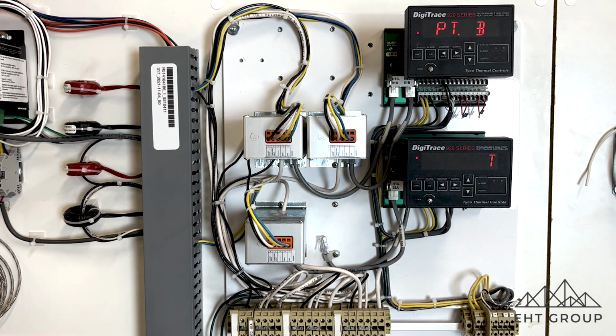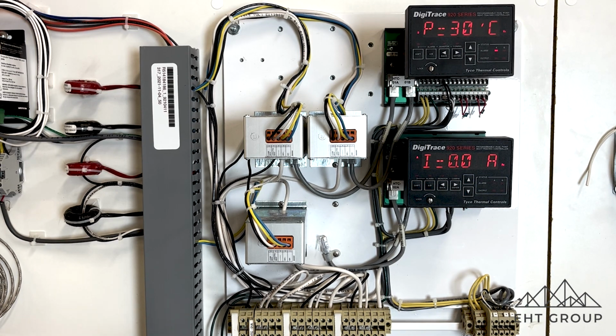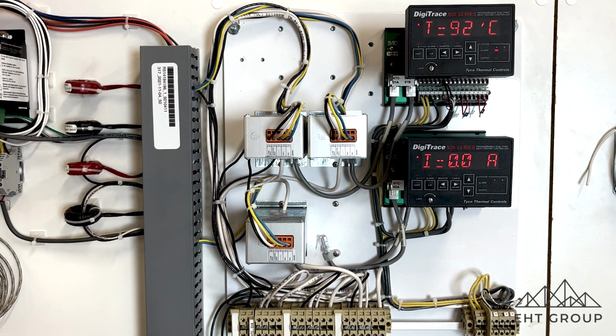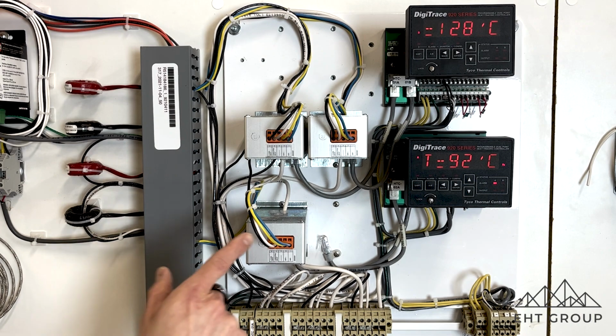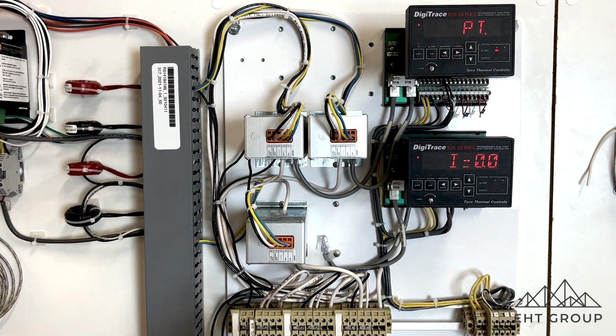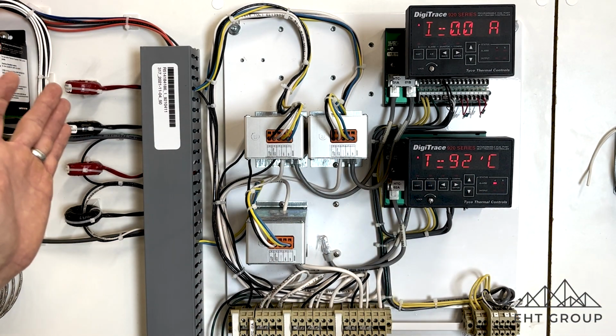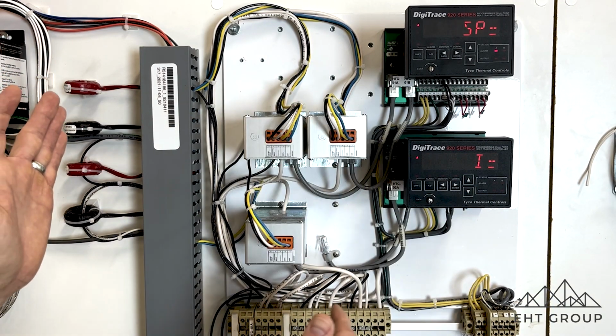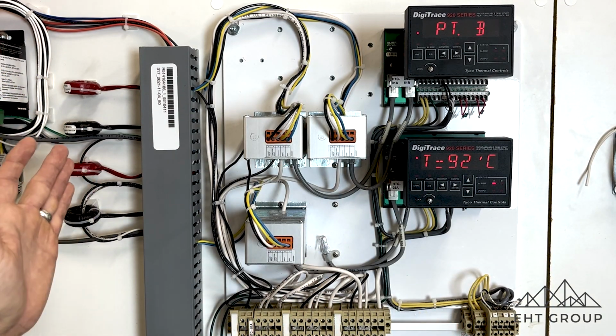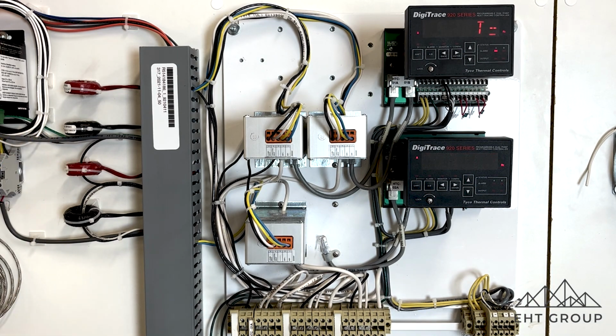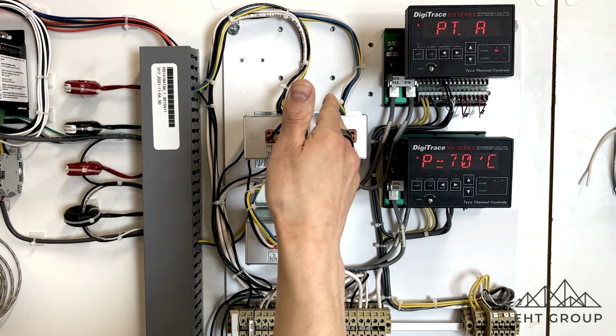Now, the risk with this, and we've seen this numerous times, is that somebody will go and do maintenance or work on circuit 1A, and they'll lock out that breaker, and then you'll lose control voltage and you'll lose power to an entire heat trace panel. So what we like to see is either the control voltage paralleled from each individual heat trace circuit. Obviously this panel, if you haven't been able to tell already, has 3 heat trace circuits on it. Or you have a dedicated circuit breaker just for control power for each one of the CT modules.